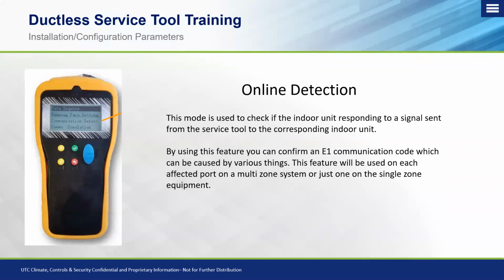Okay, so with that online detection, again, you want to hook up to the outdoor unit, L, N, and S. And by using the online detection, once you get into that submenu, go ahead and press your green check button. Essentially what it's going to do is confirm that the indoor unit is online and is responding properly from the tool that you're using to simulate the outdoor unit. Again, the tool is simulating an outdoor unit, sending a signal to that indoor unit to confirm that it's talking.